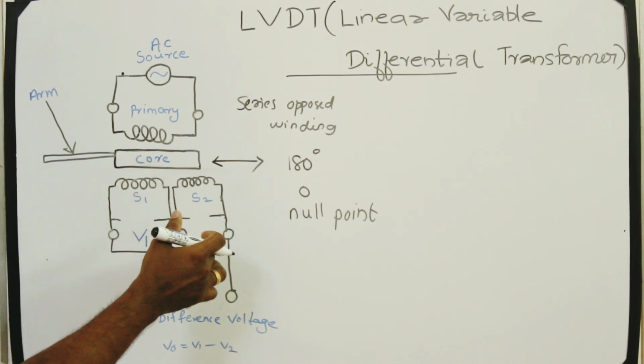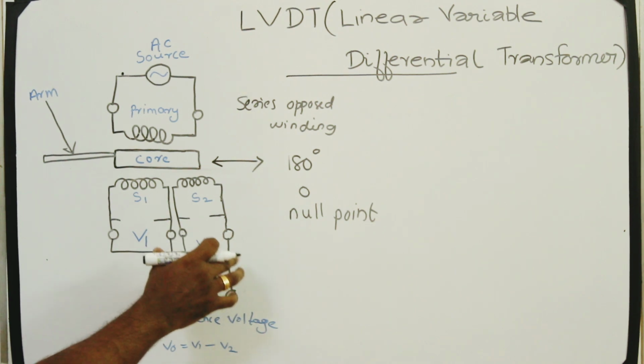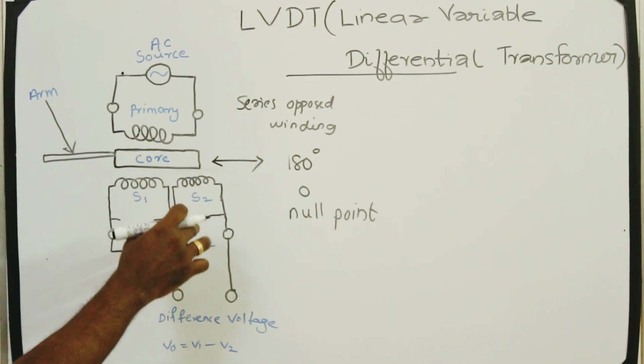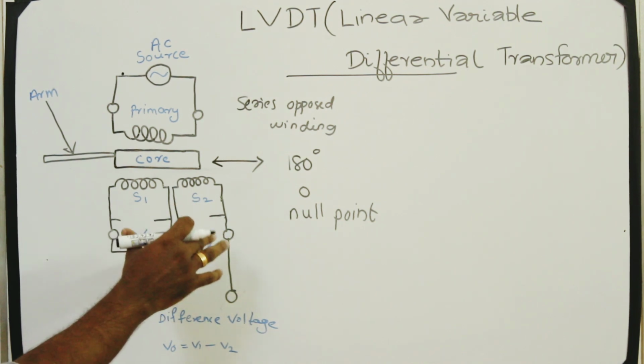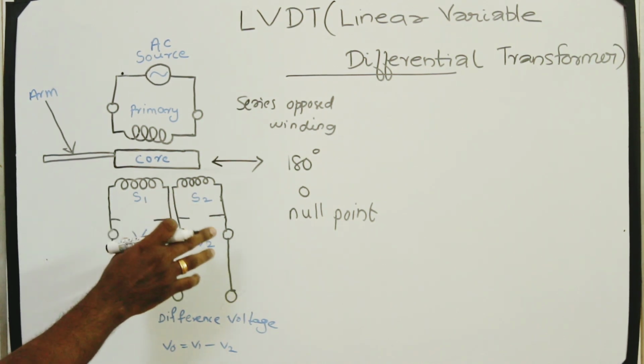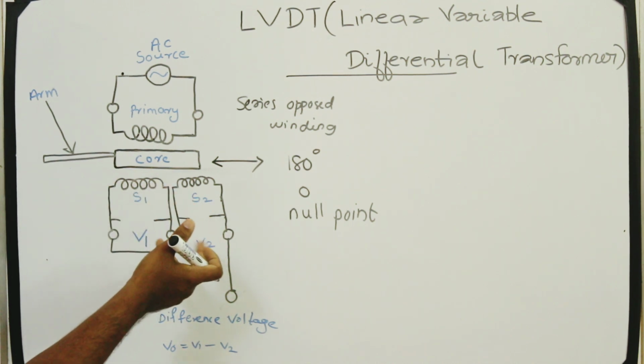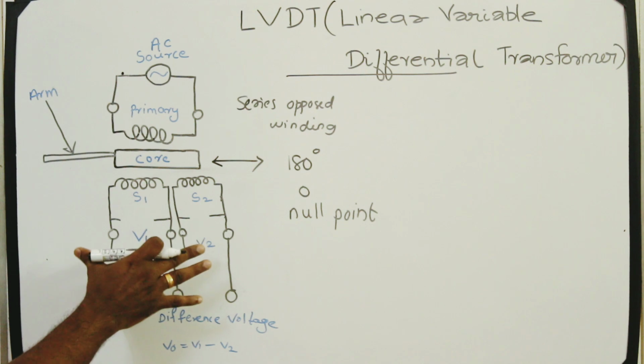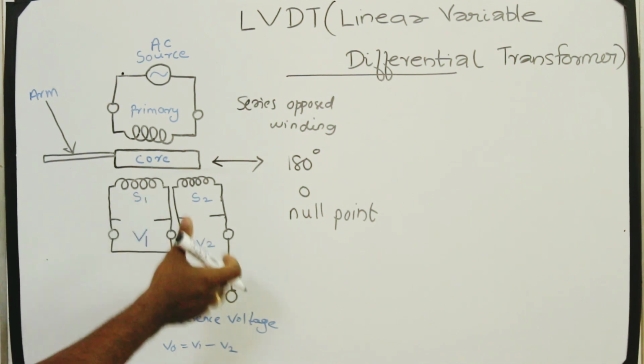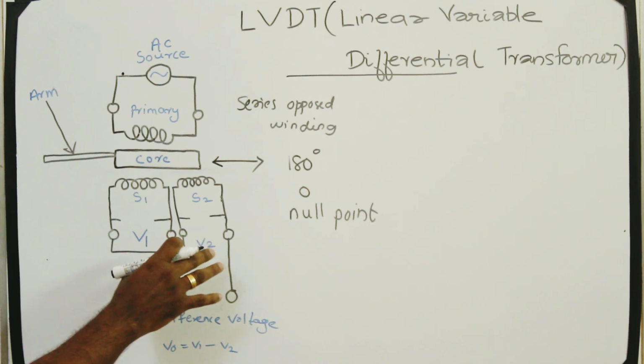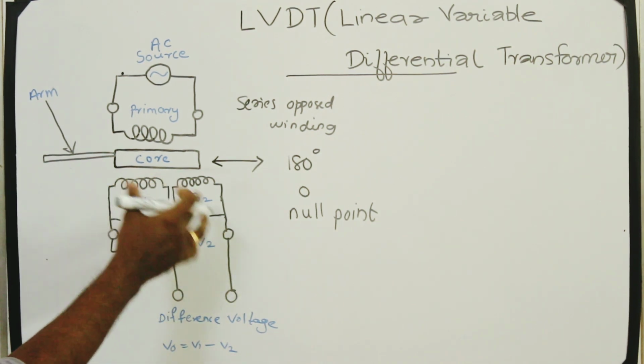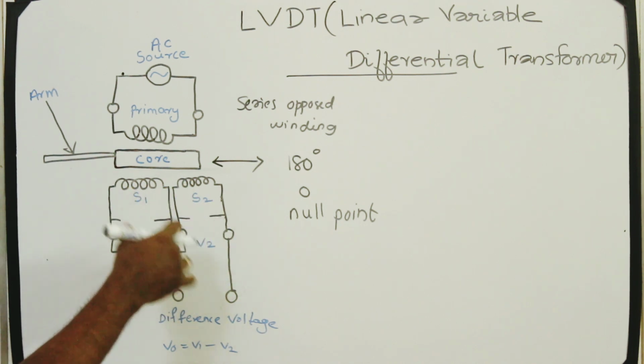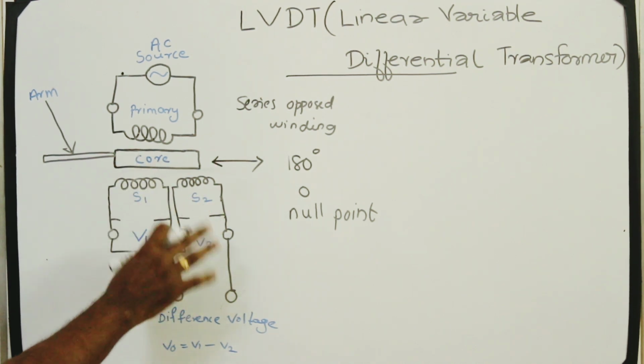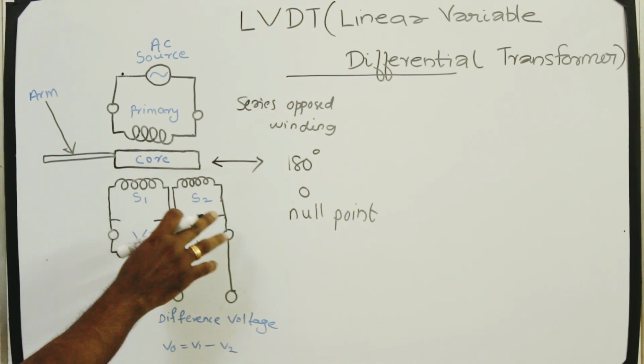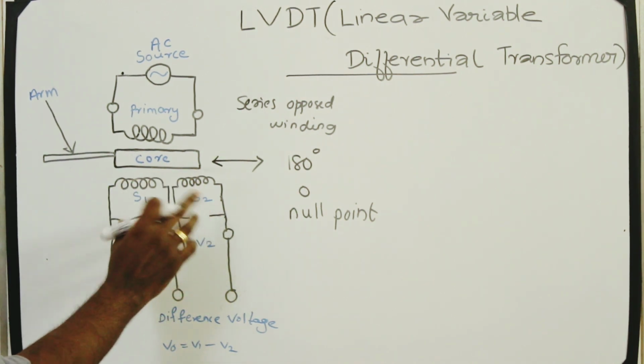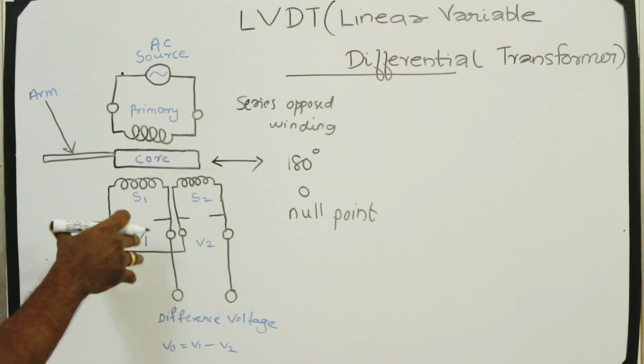Next, LVDTs have almost infinite resolution, limited only by the noise in the signal conditioner. Repeatability is extremely high. Next, LVDT devices are extremely robust since there is no physical contact and therefore no friction or wear between the moving core and the transformer bore. These are all about LVDT.